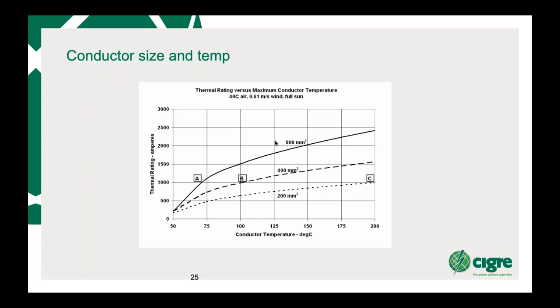Just getting on here as to what kind of conductor size and temperature you can actually design to. Here we've got, if you need a thermal rating of 1,000 amps, you can do it in many different ways. You can do it with a conductor that is like a normal ACSR conductor, and at this point here, you can get that which is around 70 degrees C. You can meet the 1,000 amps. But you can also meet it if you use a 400 mil conductor at 100 degrees C. Or you could use a 200 mil conductor at 200 degrees C.